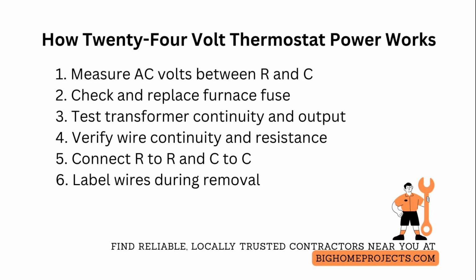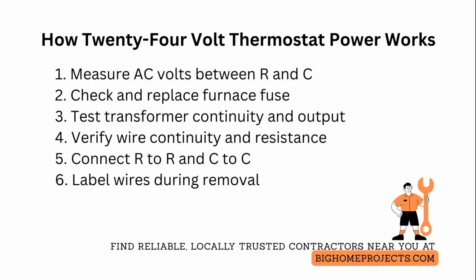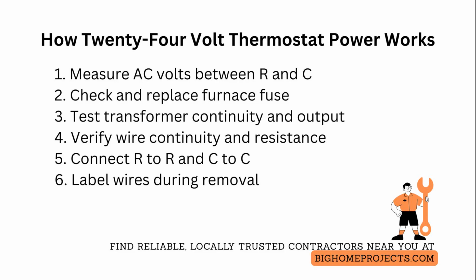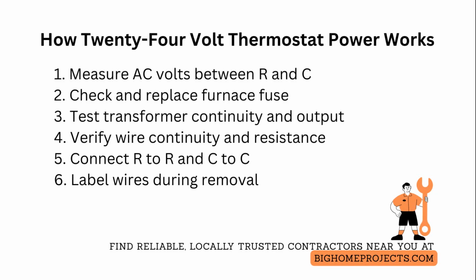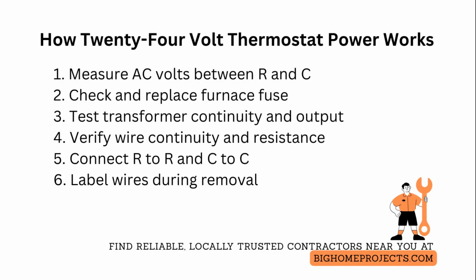Verify wire continuity between the thermostat location and the furnace by disconnecting both ends and testing each conductor with the multimeter for infinite versus near zero resistance. Anything above 50 ohms on short runs, or a reading that fluctuates, indicates a damaged or corroded conductor that needs replacement. When installing a replacement thermostat, always connect R to the thermostat R terminal and C to the thermostat C terminal, and if your new thermostat is batteryless and requires power stealing, ensure the common is wired correctly or add a common adapter kit to prevent frequent cycling and brownouts.